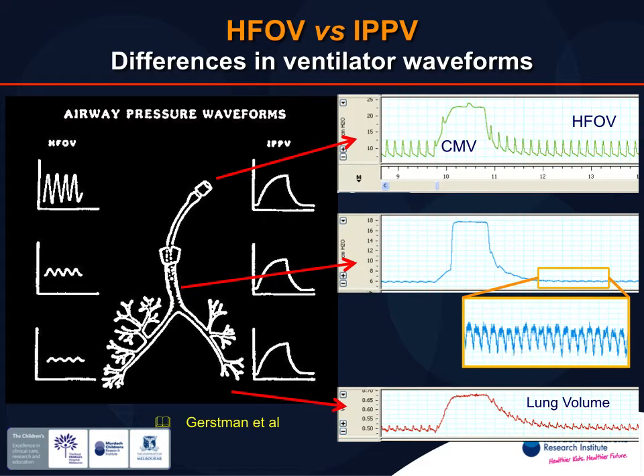But on an oscillator, you will have a very, very high delta P being applied to the lung at the airway opening. We see that. We set our delta Ps at 20, 30, 40 centimetres of water. But it is attenuated down the system such that at the alveolar level, the tidal volume and pressure change is exceptionally low. And this is a volume recording in a piglet where we've got high frequency running and then we superimpose a sigh breath with conventional.